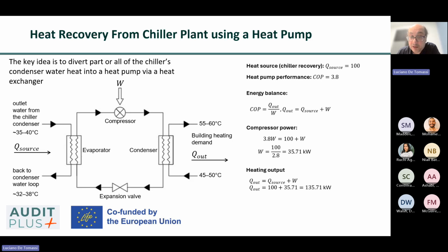to the heat pump. On the heating side, the heat pump condenser is connected to a separate heating water circuit serving the industrial facility, and this circuit is supplied with water at approximately 55 to 60 Celsius degrees, which is suitable for space heating, domestic hot water preheating, and many low to medium temperature industrial processes.